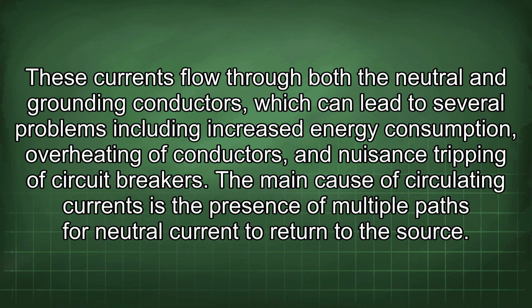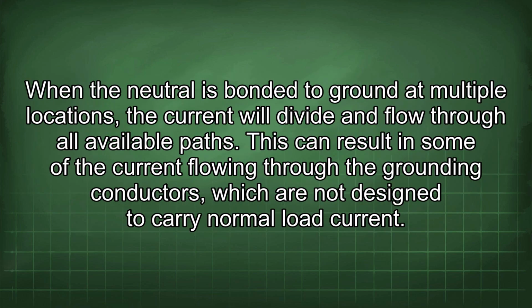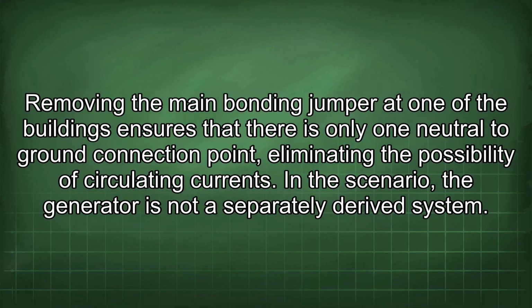The main cause of circulating currents is the presence of multiple paths for neutral current to return to the source. When the neutral is bonded to ground at multiple locations, the current will divide and flow through all available paths. This can result in some of the current flowing through the grounding conductors, which are not designed to carry normal load current. Removing the main bonding jumper at one of the buildings ensures that there is only one neutral to ground connection point, eliminating the possibility of circulating currents.